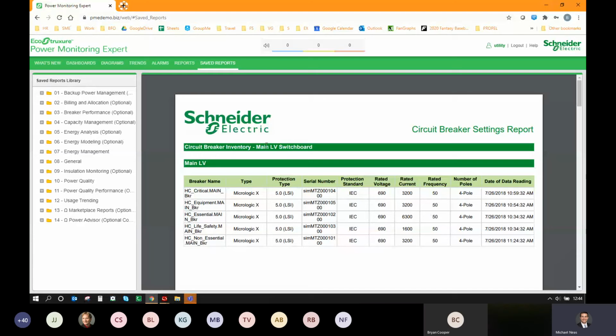So when you save the report, you go in and say, I want to subscribe to this, run on event, and then it'll bring up the event watcher drop down, and you'll see the things that you've created in there. You just select whichever one you created for this report to run. Then anytime the system sees that event come into the system, it will generate the report and send it over to the SMTP server, and then it will go out to your recipients list, which you also specify.